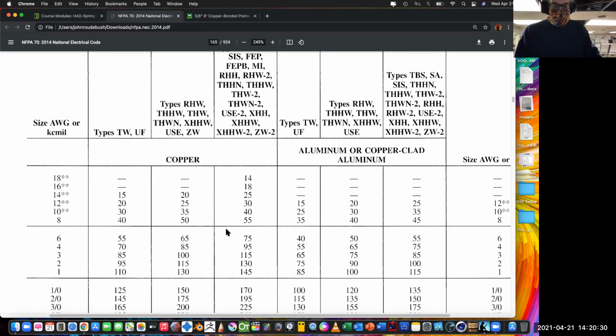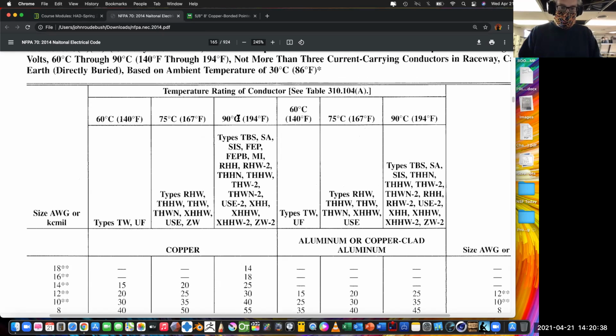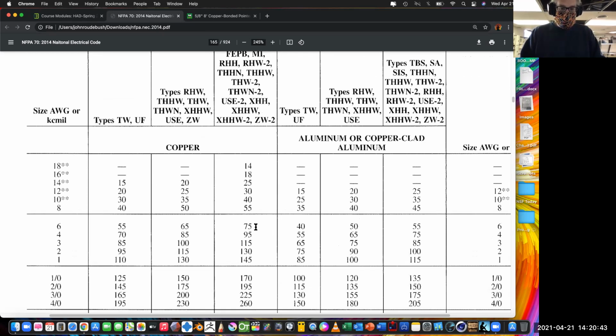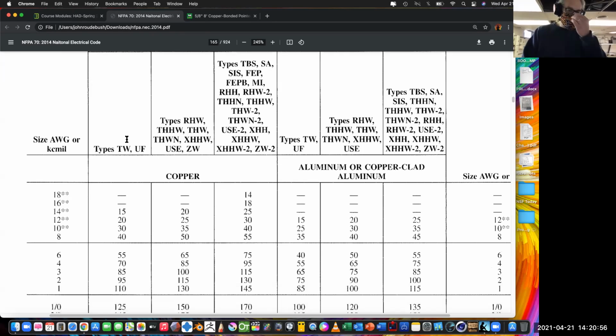We also need to understand that our terminations, according to that charge controller, can handle 90 degrees. So that means we're under this column here. But let's say we're not sure on terminations. That means we're limited to 55 amps on a number 6, but that's only if we're using this type of wire. We're not using TW or UF wire. We're using THWN-2, which we know can handle 75 amps. So because we put a limit of 60 amps on our system, we don't really worry about it, because the breaker is going to stop it at 60, but we know that wire is made to handle 75. So our wire is probably plenty big.